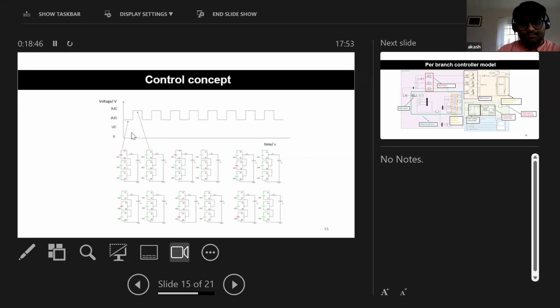In terms of balancing, let's say bank 1 and bank 2 are on, and bank 3 PWMs, going on and off for a few cycles. After a few cycles, you'll see that bank 1 and 2, which are in the baseline, have decayed more than bank 3, which was PWMing. So you switch roles — the bank which was PWMing now goes into the baseline, and one of the baseline banks starts PWMing instead. Over time, that balances out the voltages within the submodules.